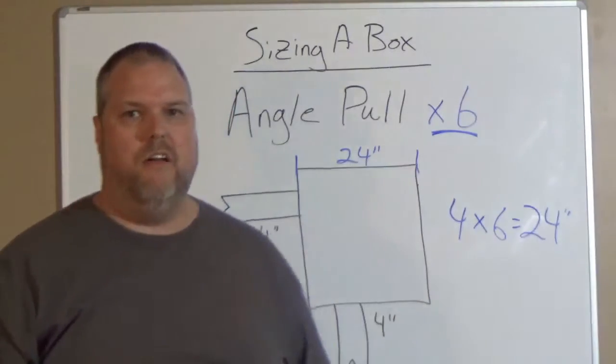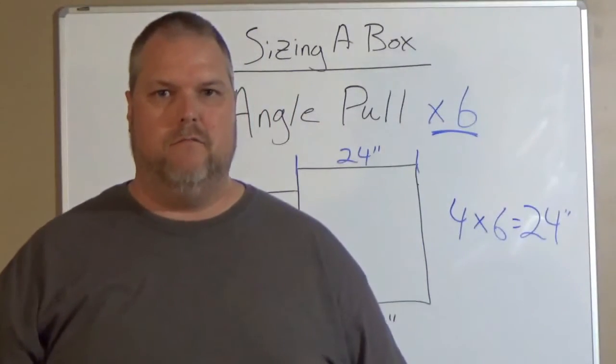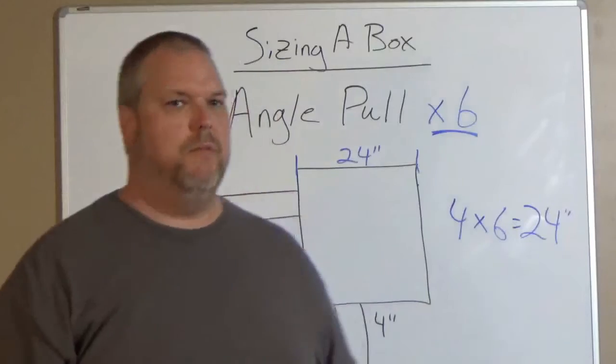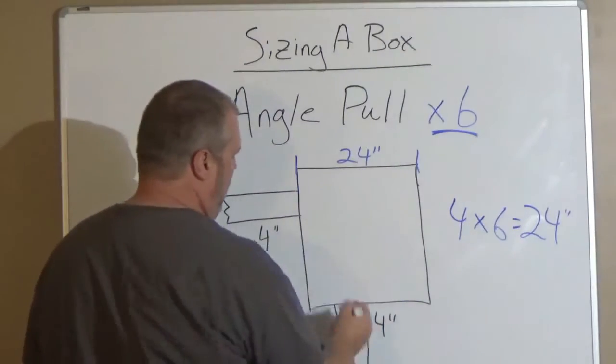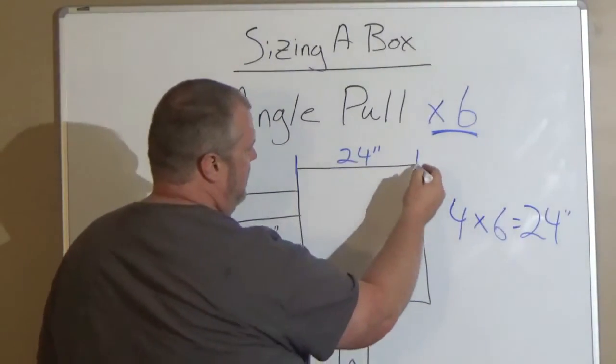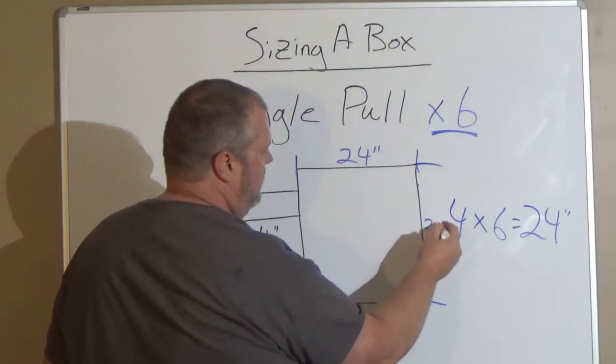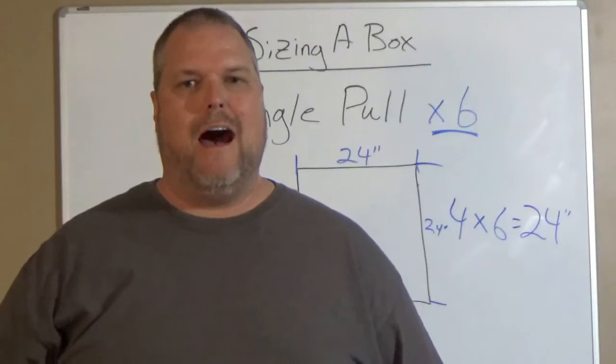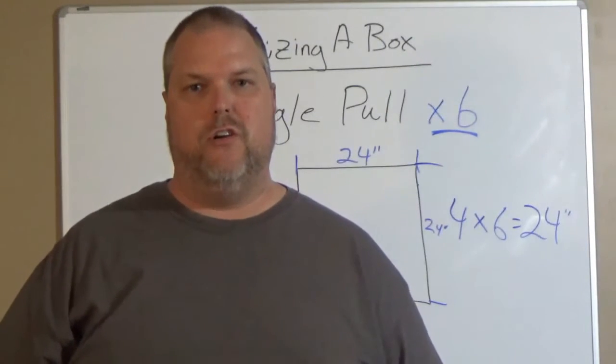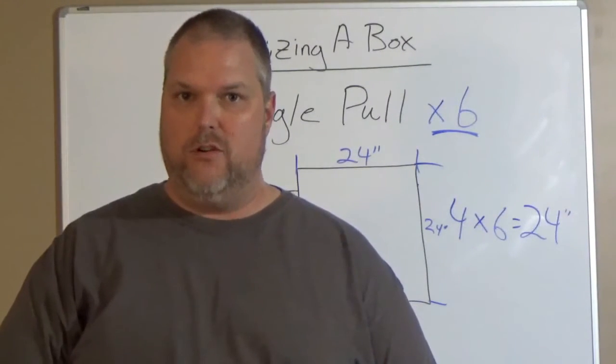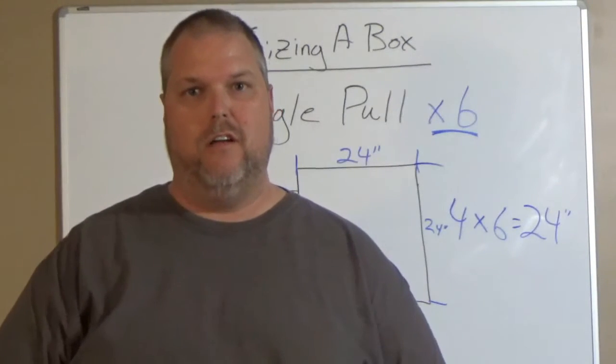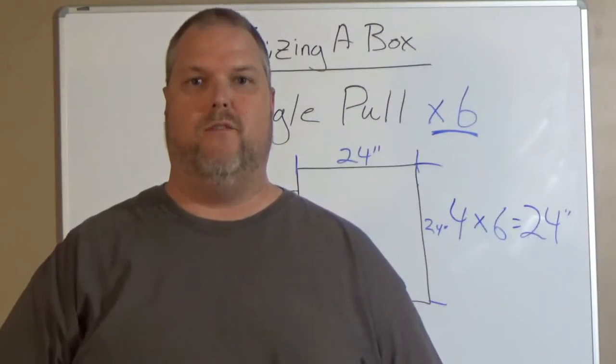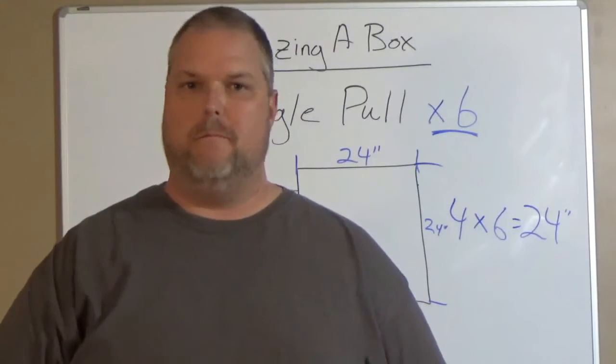Now if we're only putting one conduit in, it's very simple to complete this, because if I know I have 24 inches here, that means I have to have 24 inches here. So if I'm running a 4-inch conduit, I have to make sure that I put a 24 by 24 junction box in, period.